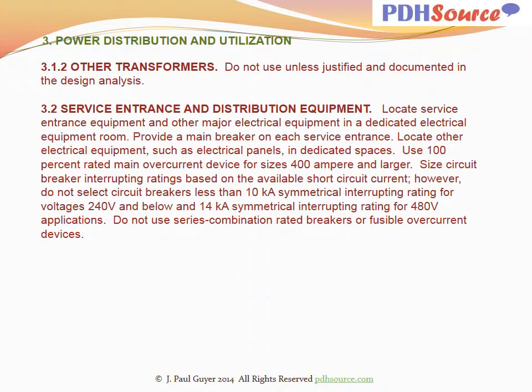With regard to other transformers, do not use them unless justified and documented in the design analysis. With regard to service entrance and distribution equipment, locate the service entrance equipment and other major electrical equipment in a dedicated electrical equipment room. Provide a main breaker on each service entrance. Locate other electrical equipment, such as electrical panels, in dedicated spaces.